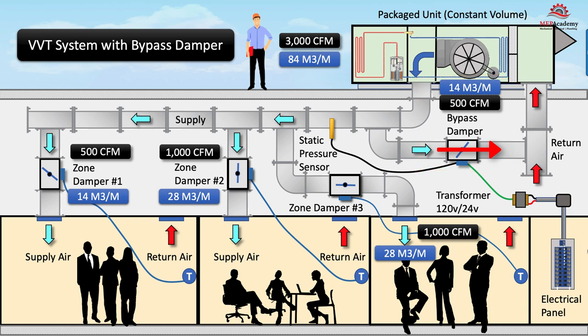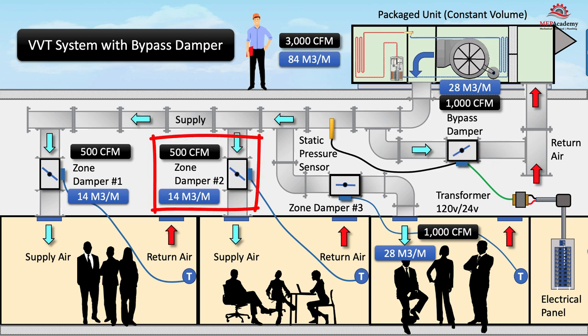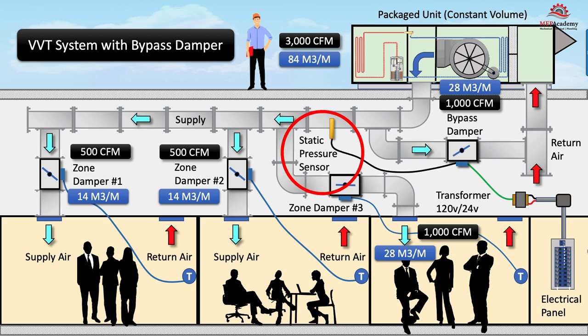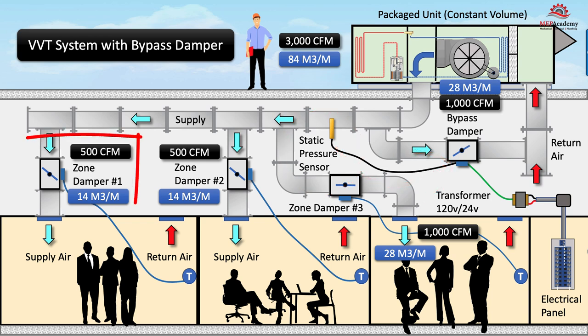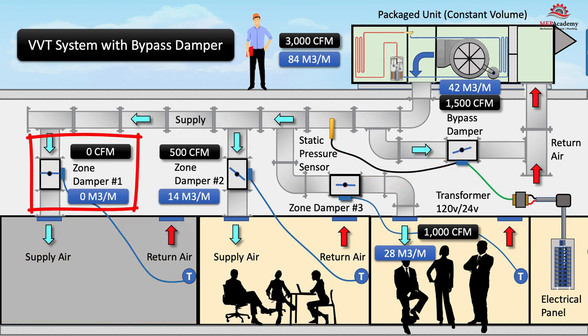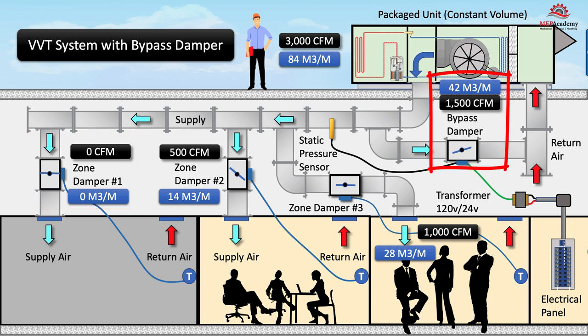If zone damper number two also reduces the amount of air delivered to the space by the same amount, the duct pressure would increase further and the static pressure sensor would send a signal to the bypass damper to open further. Then, if zone damper number one closes completely as the occupants have left the space, the bypass damper will have to bypass all the air that would have gone to that zone.